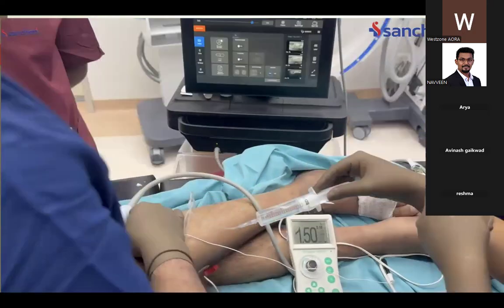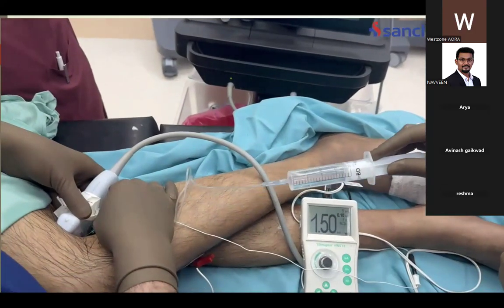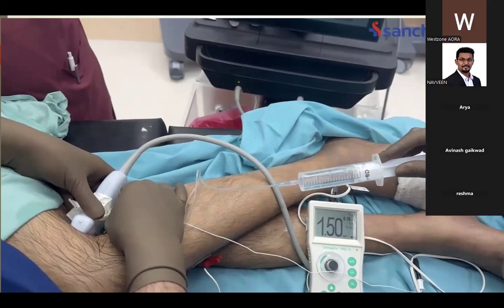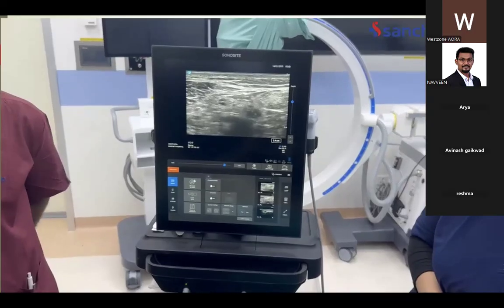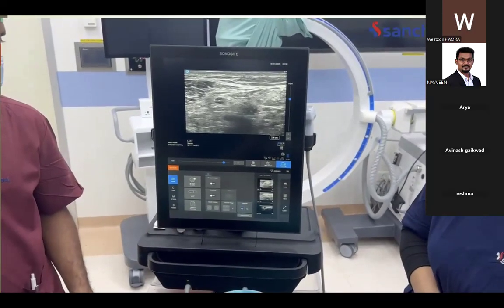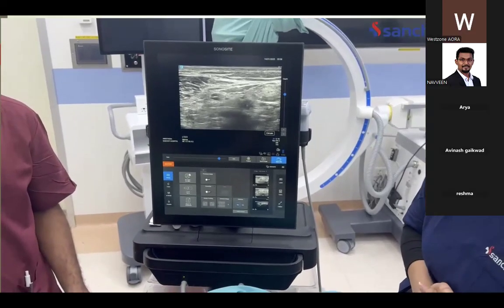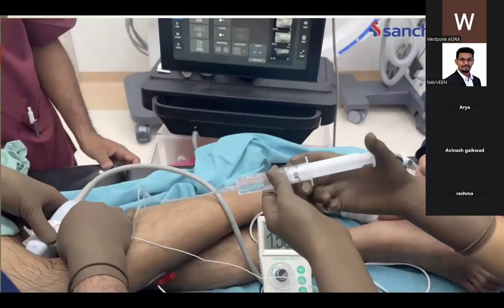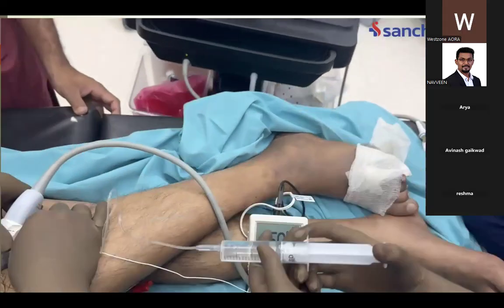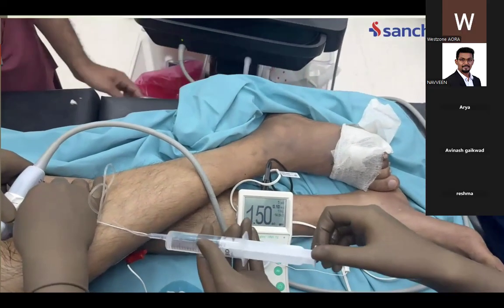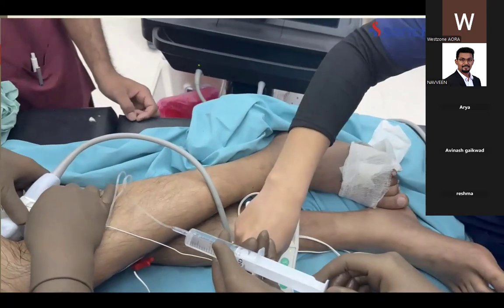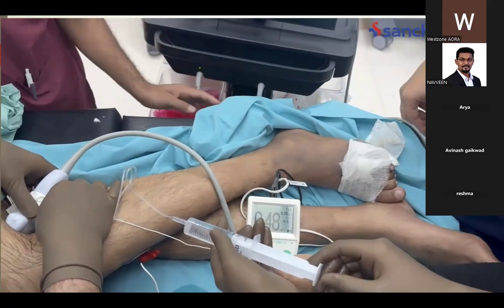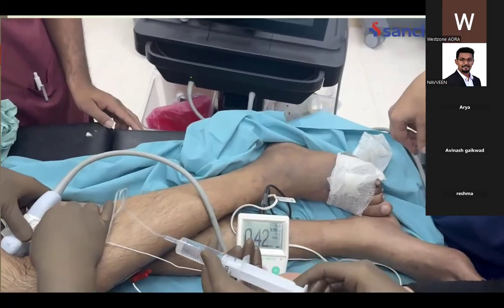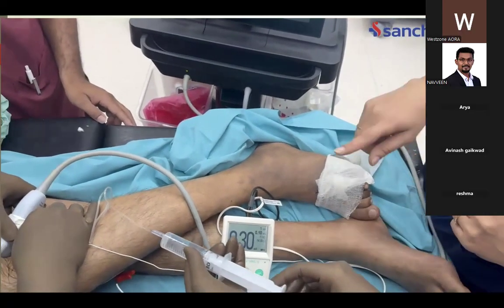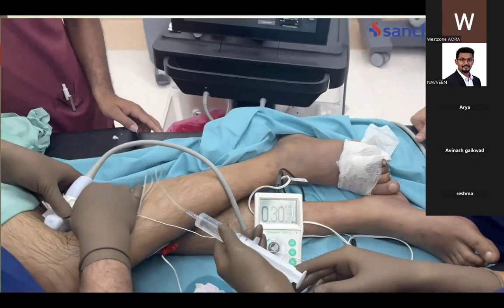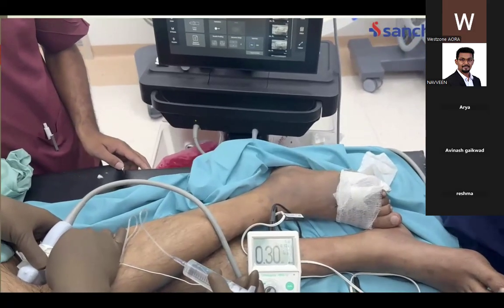So we are trying to increase the current to see if the desired motor response is obtained. Still, we are not getting that response, but now we are able to get the motor response at 1.5 milliamperes. As we reduce the current to 0.9, the motor response is still present. At 0.48, it's still present. At 0.4, 0.3, the motor response is decreased. So sir is withdrawing the needle a little bit, and then the drug is being injected.